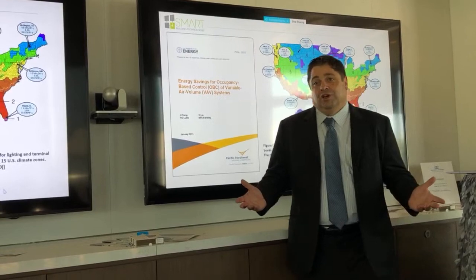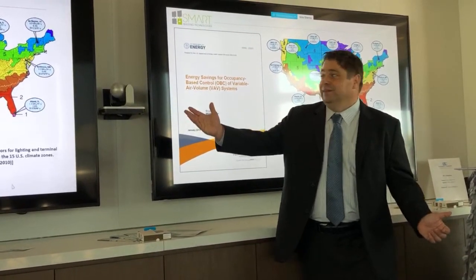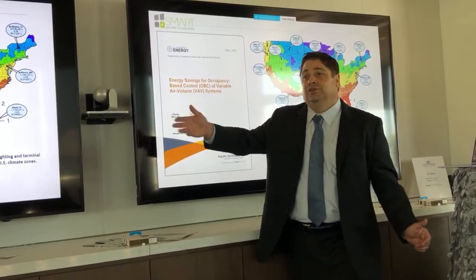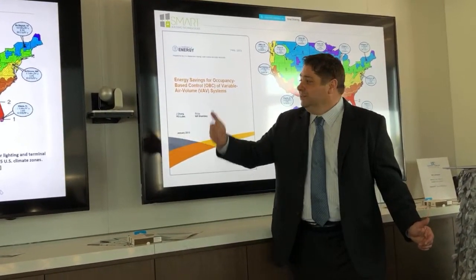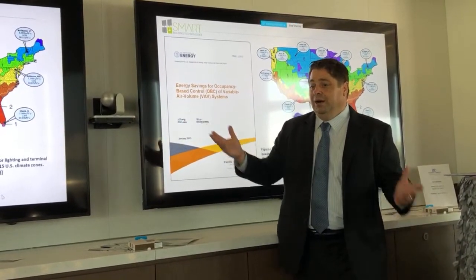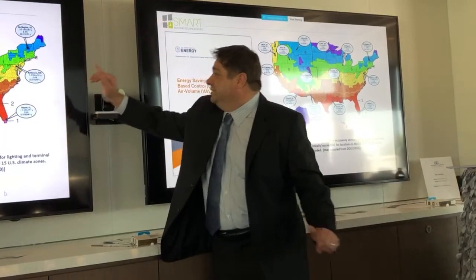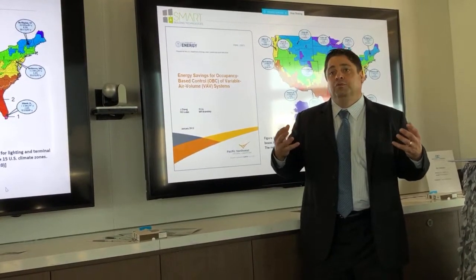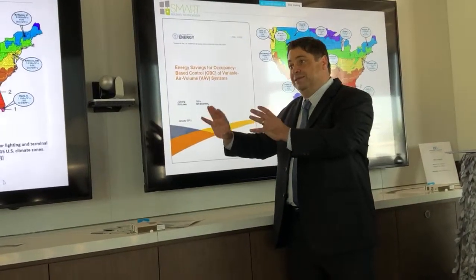Why do you do it? So the easiest answer has always been energy in the past. And this is from the Department of Energy, showing that in Baltimore, on average, if you connect the lighting system to the HVAC system and use the occupancy sensor, you'll save a little over 6 cents a square foot on energy. Actually, 7 cents, it's 6.5%. And that typically will help you fund the project in doing the unification. And that's always what's been the driver in the past.